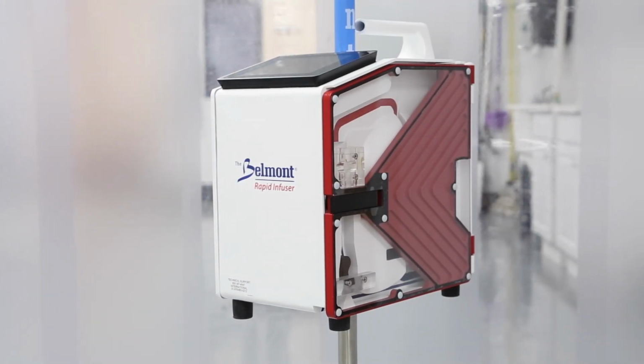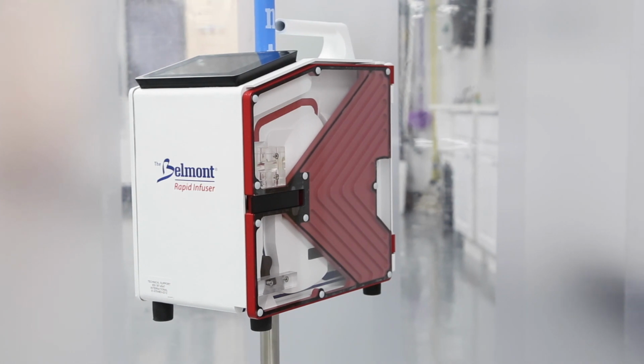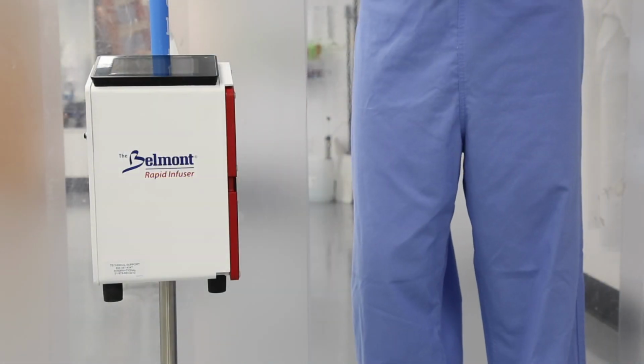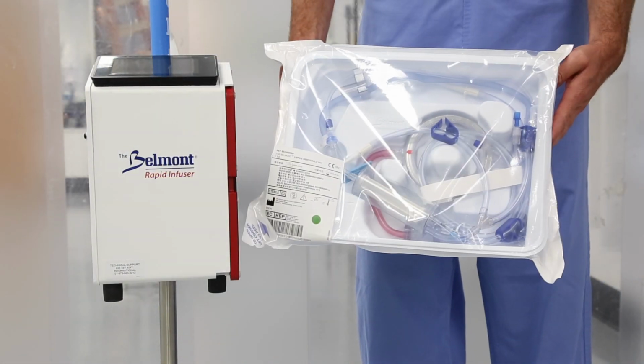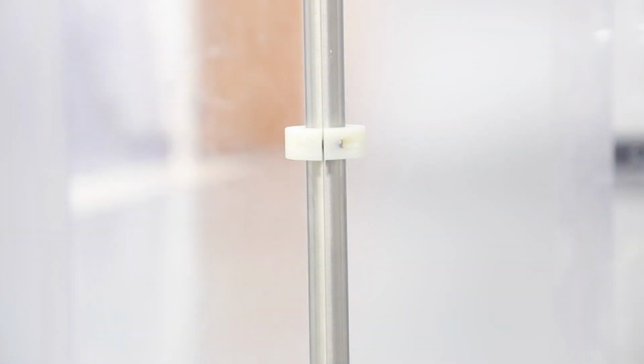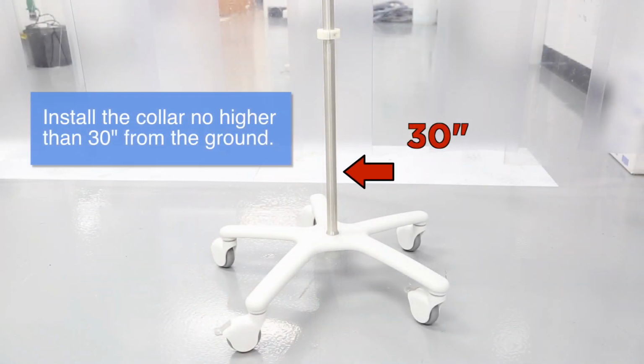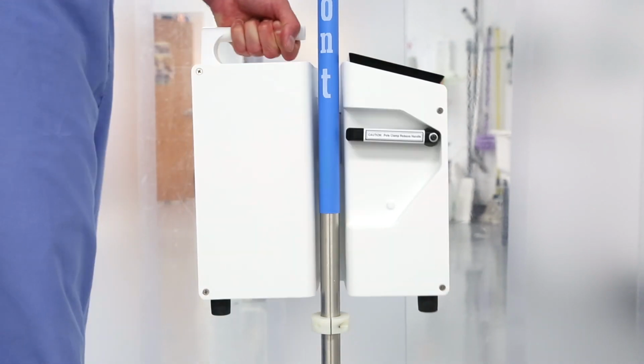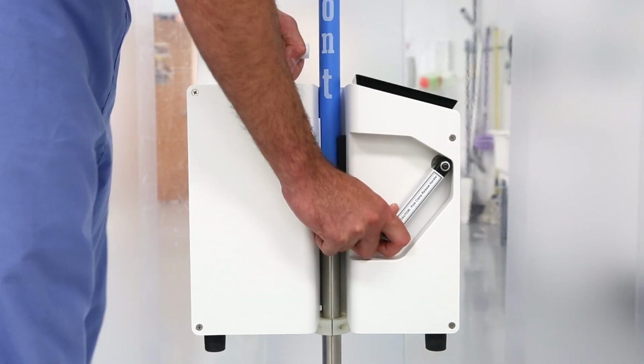Belmont Rapid Infuser RI-2 consists of two main components: the control system, which is mounted on an IV pole, and the disposable set. First, install the collar on the IV pole just beneath the system, no higher than 30 inches from the base of the IV pole. Mount the system above the collar by pushing down on the pole release handle.